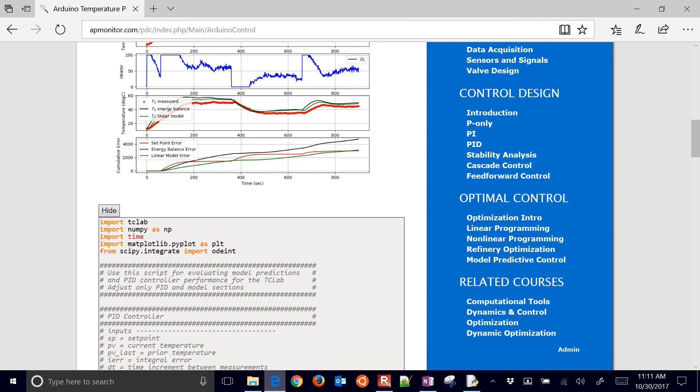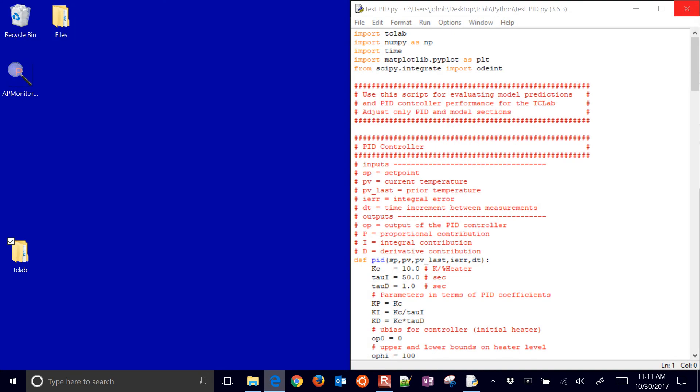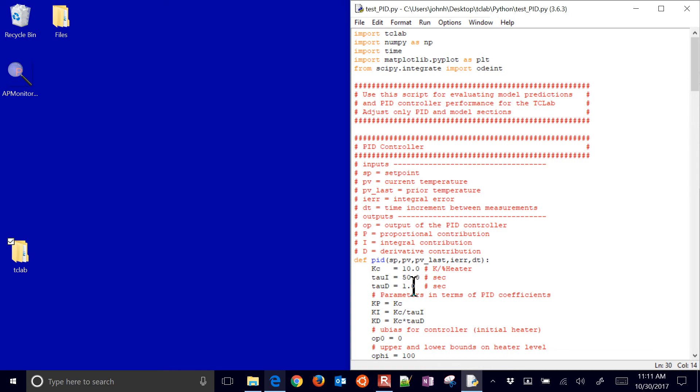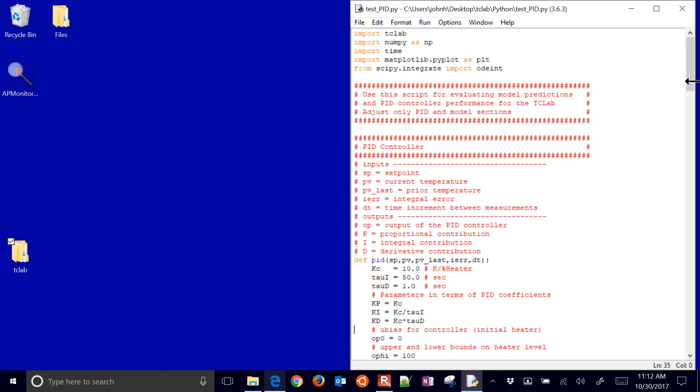So let me just go ahead and show this, my version of it. This is the one that you can download. I used a Kc of 10, a Tau I of 50 seconds, and a Tau D of 1. And that translates into these Kp, Ki, and Kd values.